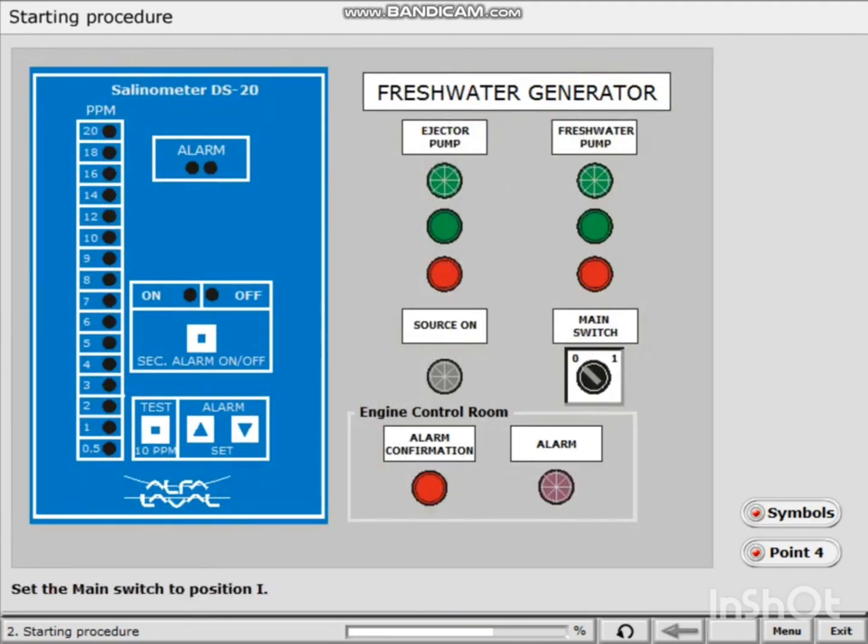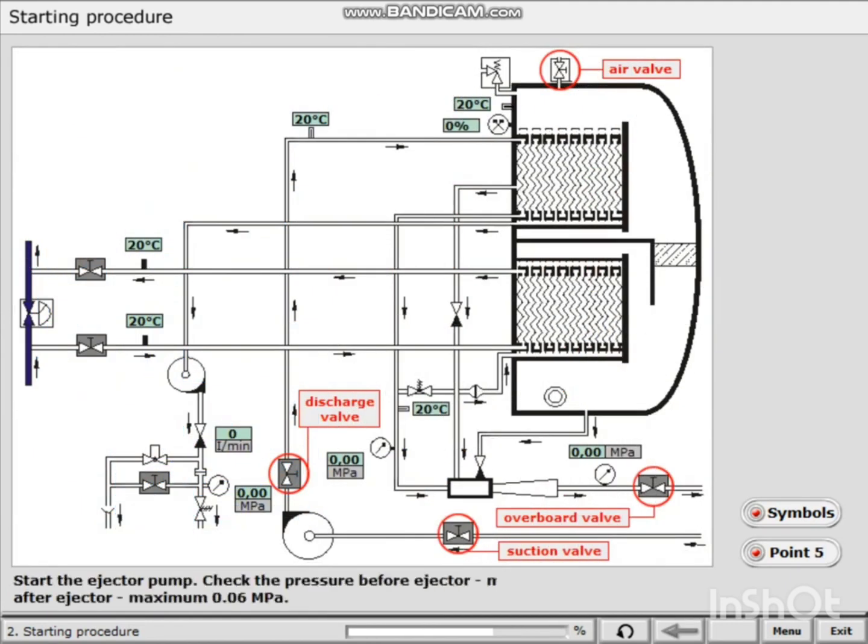Set the main switch to position 1. Start the ejector pump. Check the pressure before ejector: minimum 0.28 to 0.3 MPa. After ejector, maximum 0.06 MPa.